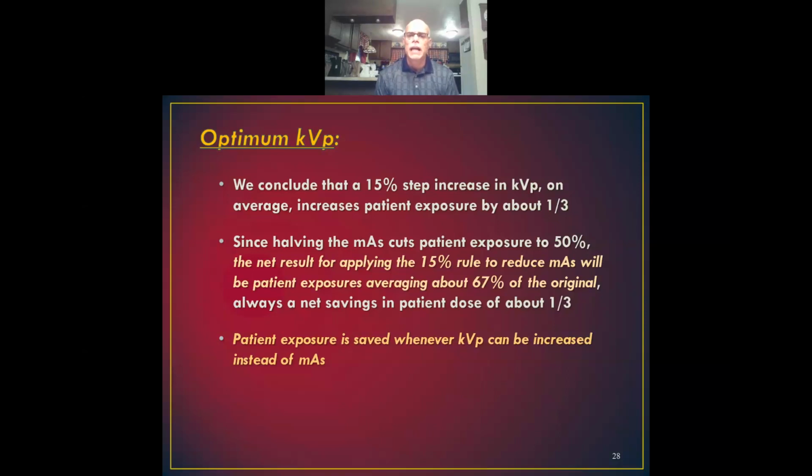Patient exposure is saved whenever KVP can be increased instead of mAs. So we are now in the world of technology where the systems can handle higher KVPs. We encourage you guys to use higher KVPs for this reason.